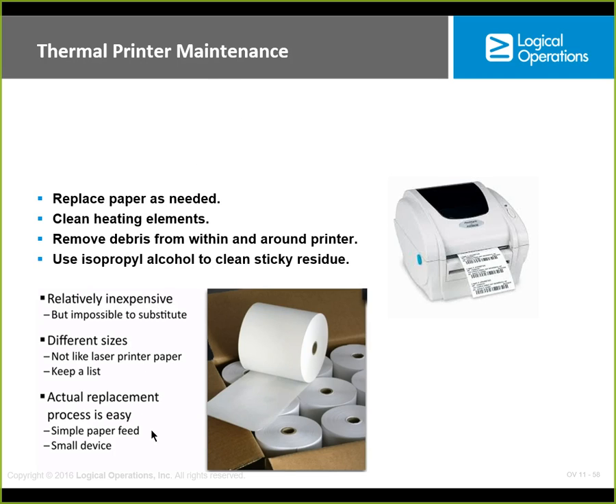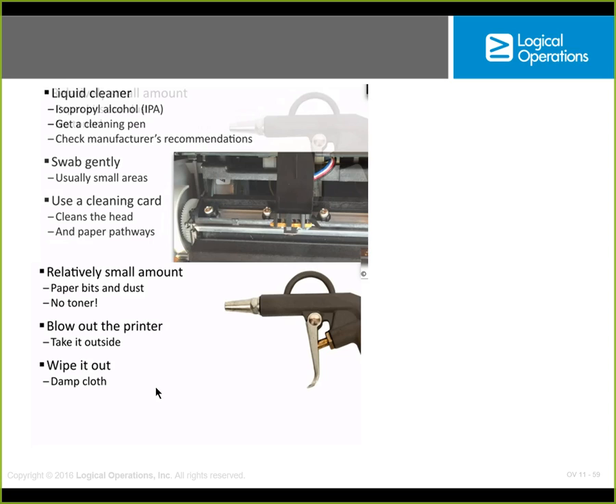Thermal printers: replace the paper, clean the heating elements, remove the debris that's inside it. Isopropyl alcohol removes sticky residue. Paper is relatively inexpensive, but impossible to substitute. You have to have the right paper and the right size for the device itself. Actual replacement is normally going to be pretty easy. You take the top off and put the new roll in, much like in a calculator.